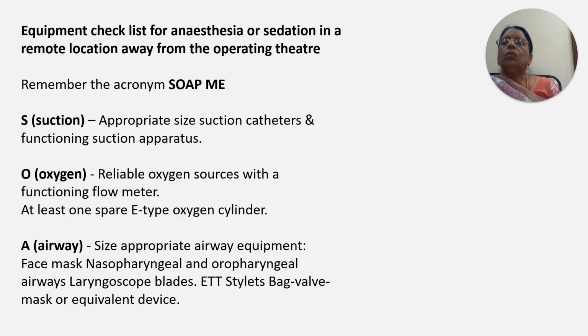So what is the equipment required for anesthesia or sedation in a remote location away from the operation theatre? We have to check each and everything, whether it is available or not. So remember the acronym SOAP-ME. S is for suction: appropriate size suction catheters and a functioning suction apparatus should be available. O is for oxygen: a reliable oxygen source with a functioning flow meter. At least one spare E-type oxygen cylinder should be ready.